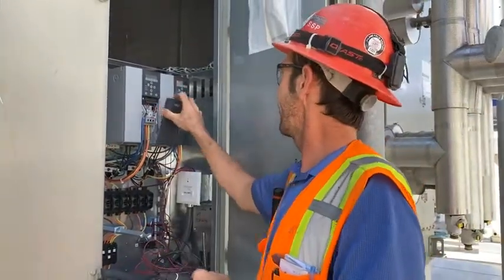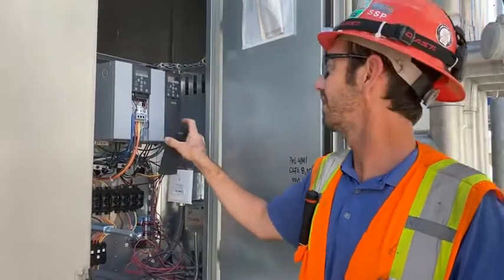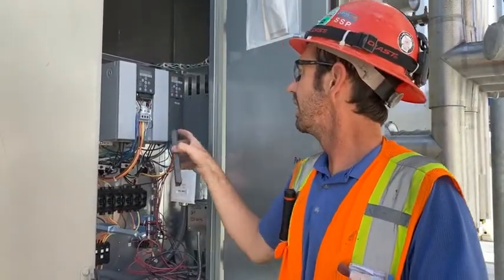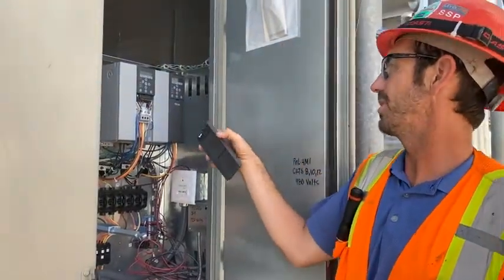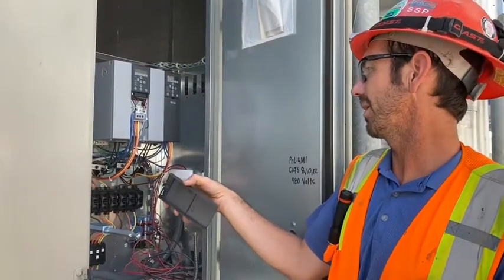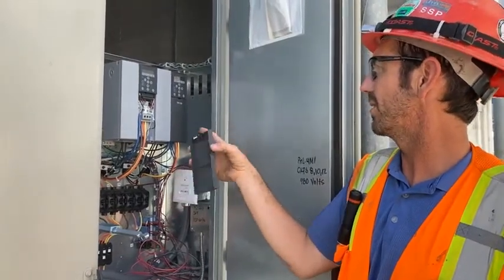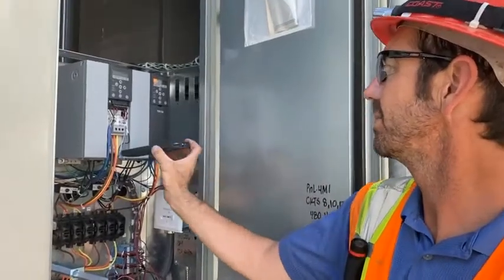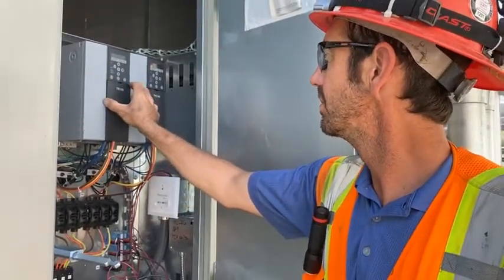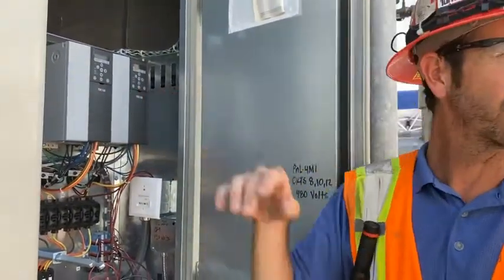I'll put this back on. Any questions with under here? The brown, orange, yellow, that is high voltage going out to the motor. We're not running the unit right now. There's no power coming out of the drive. But it is 480, okay?